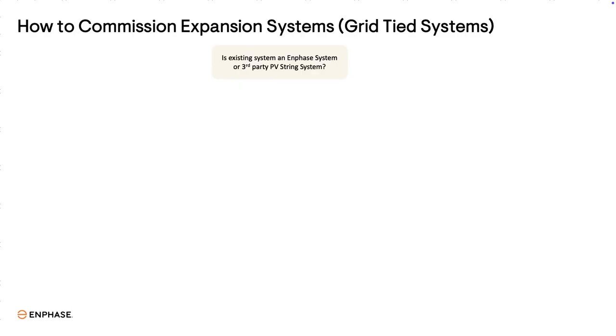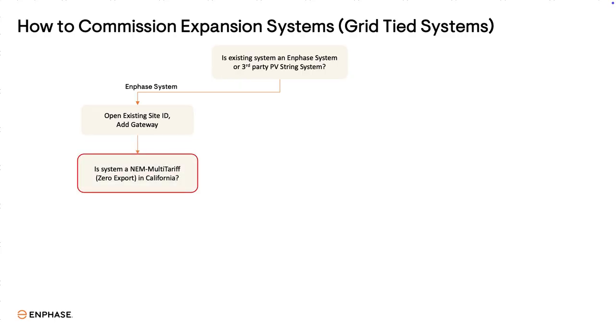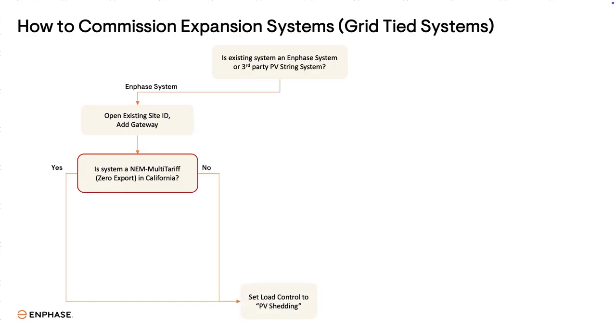Here's the commissioning flow for grid-tied expansion systems. First, determine if the existing system is an Enphase system or a third-party inverter system. If it's an Enphase system, open the existing Site ID and add a gateway. You'll be asked if the system is NEM multi-tariff zero export in California — select yes or no. Regardless of the answer, you will set load control to PV shedding. Please note, the term PV shedding is just a configuration name. Since the system is grid-tied, there is no shedding of the PV. The option is chosen to inform the system that existing PV is connected to the load control port in the combiner.